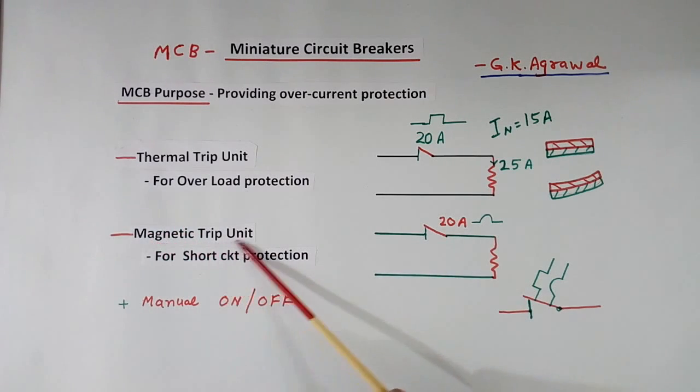And this magnetic trip unit will have a coil, a magnetic coil. Because of that, it will trip. That will be very fast, generally will operate in a few milliseconds.